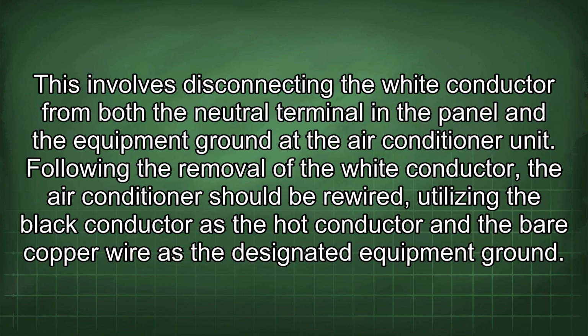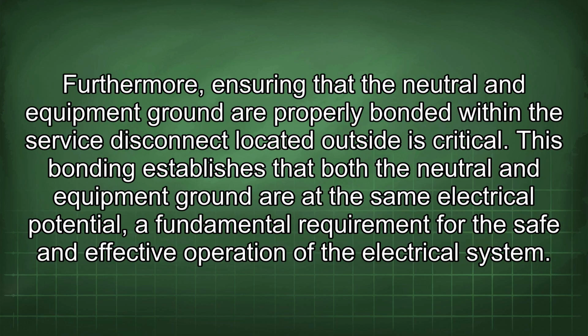This involves disconnecting the white conductor from both the neutral terminal in the panel and the equipment ground at the air conditioner unit. Following the removal of the white conductor, the air conditioner should be rewired, utilizing the black conductor as the hot conductor and the bare copper wire as the designated equipment ground. Furthermore, ensuring that the neutral and equipment ground are properly bonded within the service disconnect located outside is critical. This bonding establishes that both the neutral and equipment ground are at the same electrical potential, a fundamental requirement for the safe and effective operation of the electrical system.